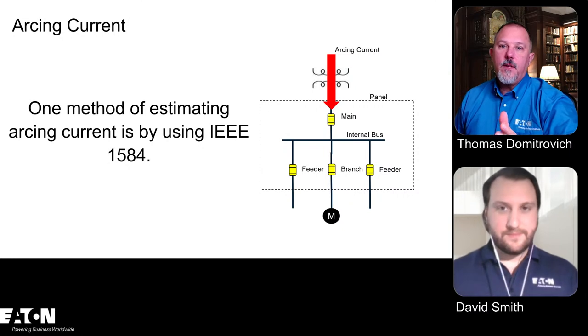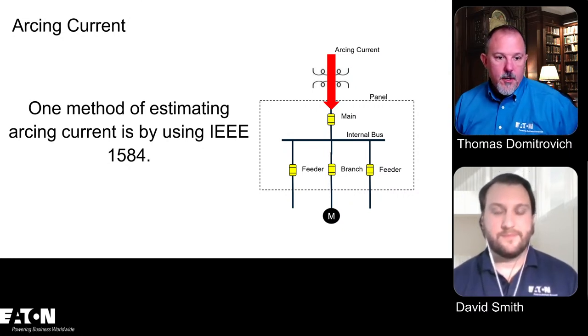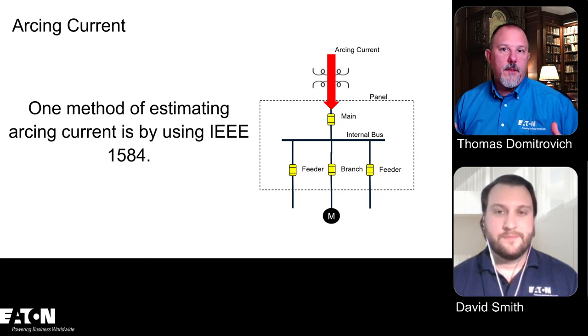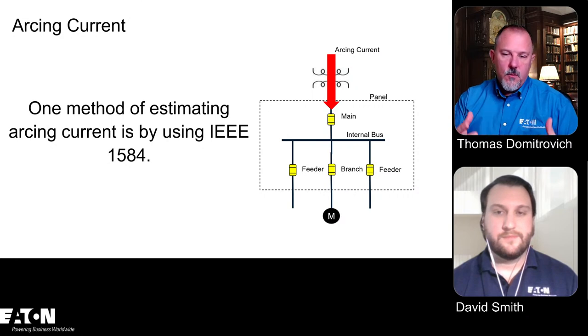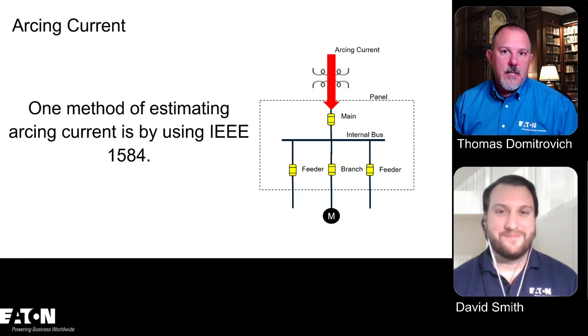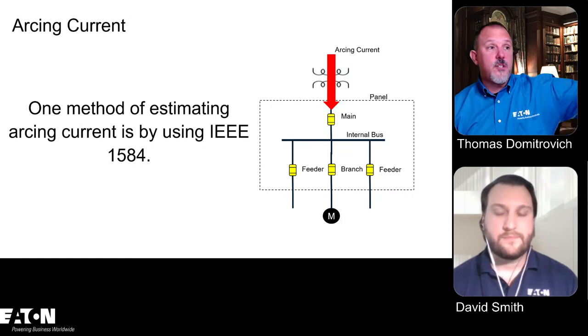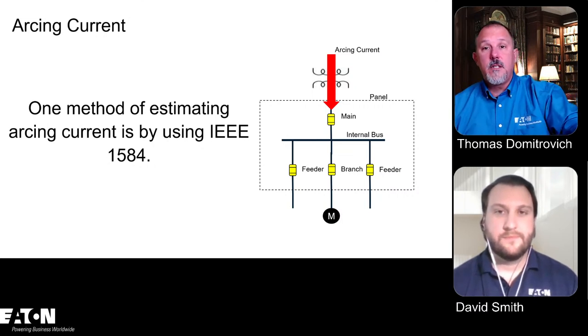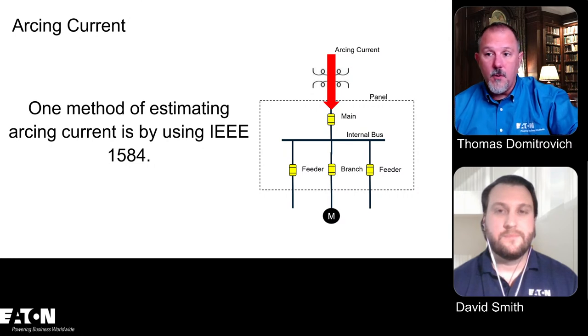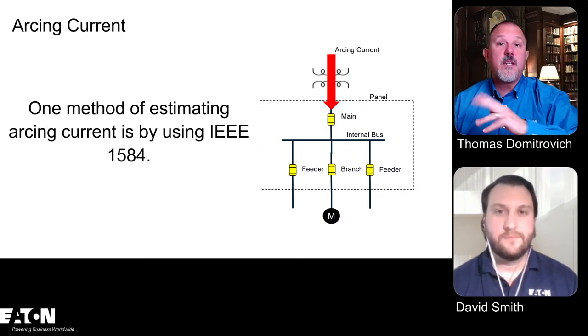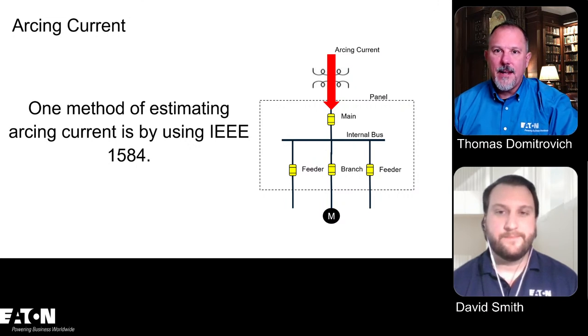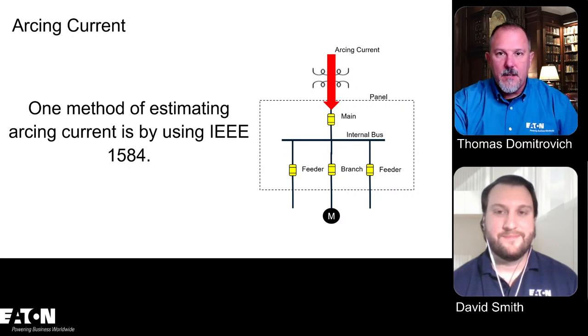And you know what? The table method in 70E, I'll argue, and I've gone back and forth with Jim Dollard on this until I finally realized, when I think about arcing currents and whatnot, in 70E you have the table method, which, David, I don't know if you're familiar with it, doesn't use the arcing currents and clearing times. Basically, it says if you're downstream of a molded case circuit breaker and your available fault current is less than this number and your voltage is this number or less and it's a panel board, this is how you dress. And you go, well, wait a second, I should be doing math. I should be doing an arcing current. I should be calculating this. I should be comparing clearing times.